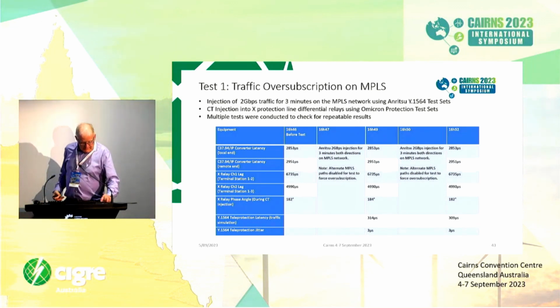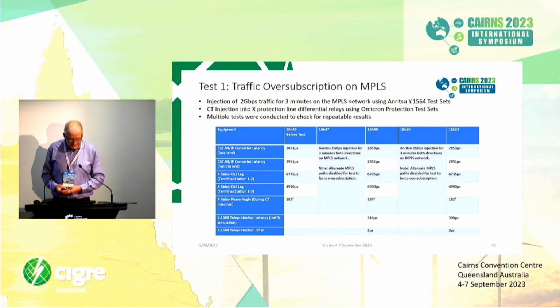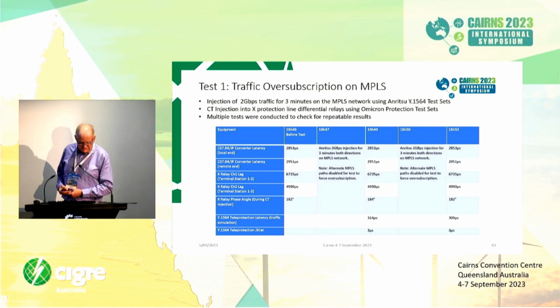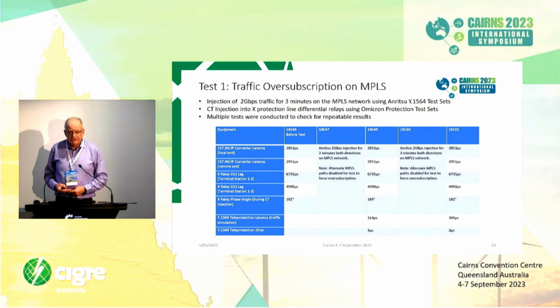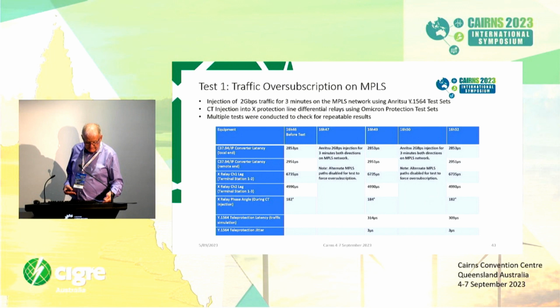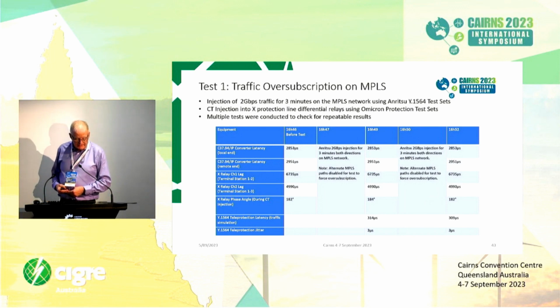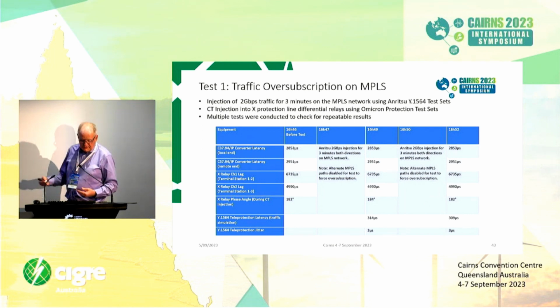So if you look at the latency figures, the top two are the C37.94 converter latency as measured on the actual IP converters at each end. So we're getting very consistent results there, no real change between the different tests as we injected the oversubscription in the middle there. The relays also measure the channel lag. This is the round trip time. Once again, you can see there the X relay channel 1 lag didn't really change between tests. So before the test it was the same as after the test, right?